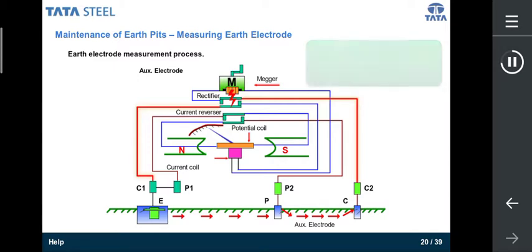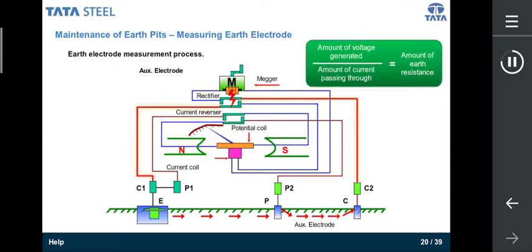So, to measure the earth resistance, the voltage generated needs to be divided by the amount of current passing through. This division will give an idea about earth resistance. Therefore, the megger is crucial in finding out the earth electrode resistance measurement. It is also referred to as an earth testing megger. This is all about the earth resistance measurement process.